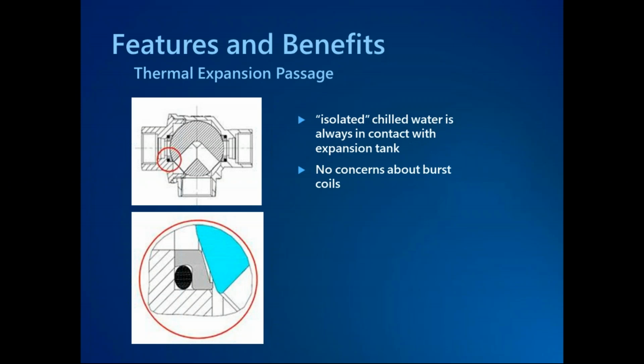Another feature that we need to look for in a six-way, and this is kind of hit or miss. Some manufacturers incorporate something like this, some do not. It's the thermal expansion passage. When you go from full cooling mode, so we've got cold water flowing through your chilled beam zone, to full isolation, and you don't have any type of thermal expansion passage, then the cold water is trapped up in the plenum in this piping. Hot air naturally rises, your water is going to slowly warm, and with no place for this expansion to take place, it's going to increase the pressure and potentially burst the pipe.